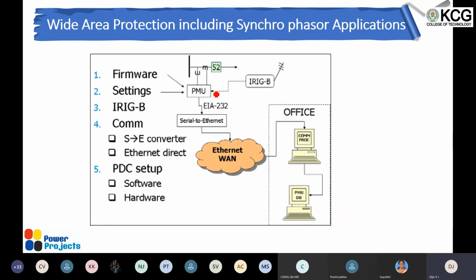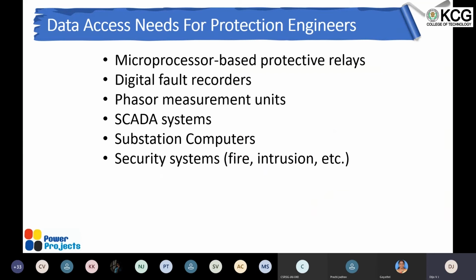So this was basically what we were discussing: the communication related topics with respect to a protection engineer. Now it's clear that a protection engineer should have access to microprocessor based protection relays, digital fault recorders, phasor measurement units, SCADA systems, substation computers, and security systems, fire, intrusion, etc.